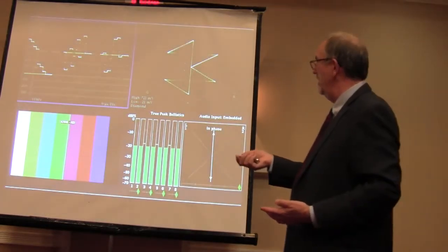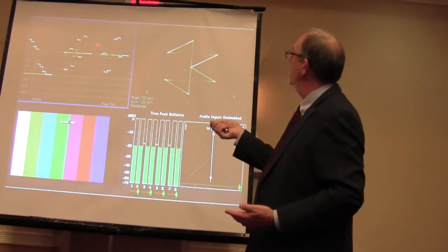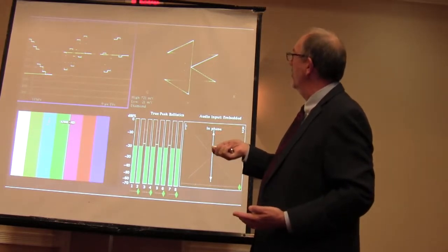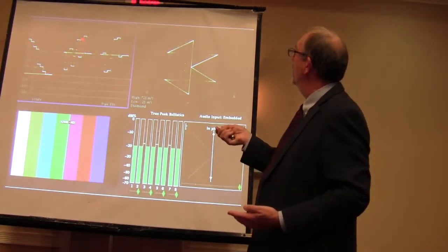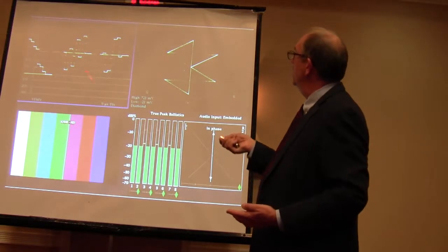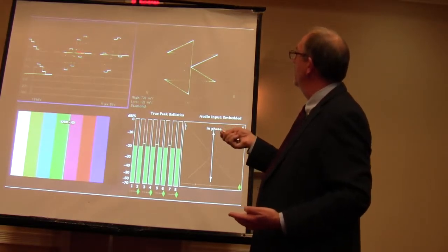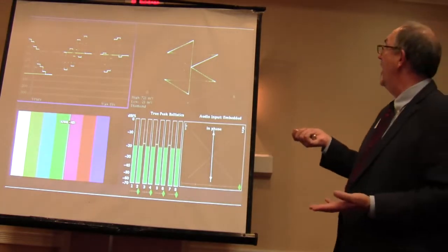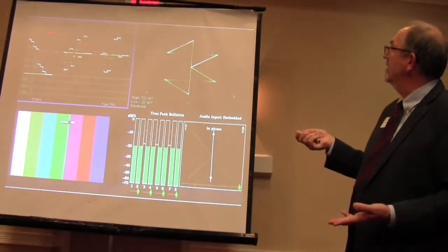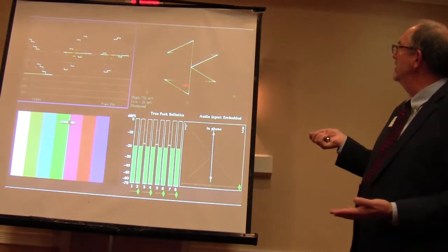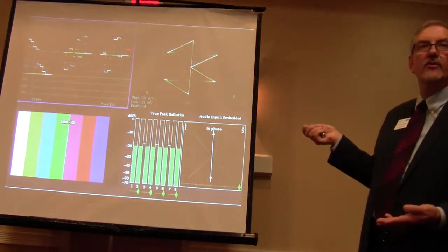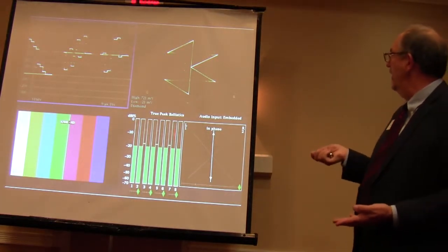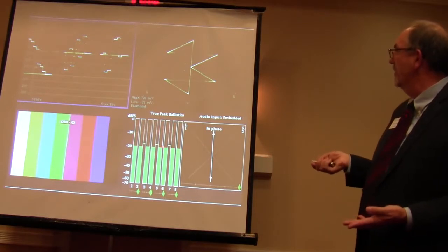You're looking at color bars here, and you can see this is the pattern on this oscilloscope, and we're looking for where the blacks fall and where the whites fall, and each one of these colors should be falling at a certain point. And if they're not, we know that there's equipment that needs to be adjusted or replaced or what have you. Same thing over here. This is kind of talking about luminance. This is talking about chrominance. Is the green green or is the green red? All right? And then again, we've got audio ballistics down here.